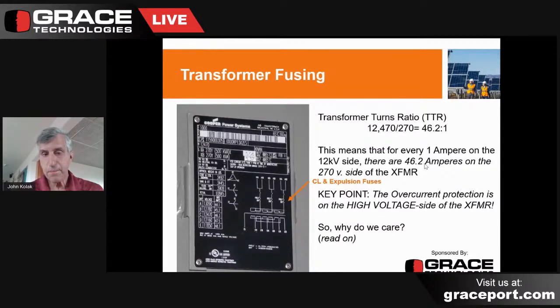The fix for that is to put a second fuse in series there, which is a current limiting fuse. So why this is important is if you had a high voltage fault on the primary winding, the current limiting fuse would clear that expeditiously. It was normally very good at clearing those high fault current events. And the expulsion fuse would clear low voltage winding faults on the system. So this is also important to keep in mind. So again, having the 2 fuses in series with each other is critically important.